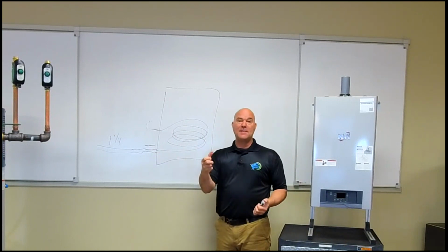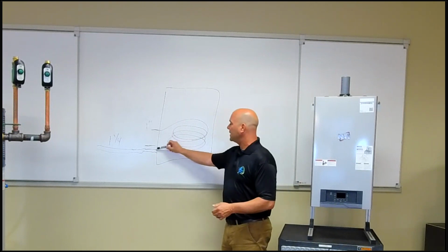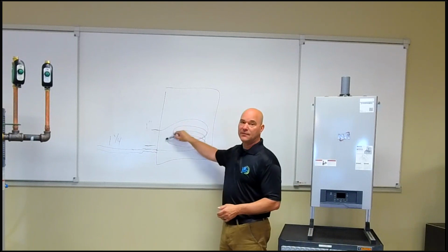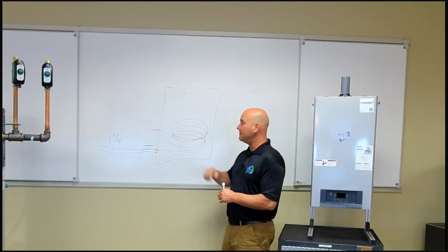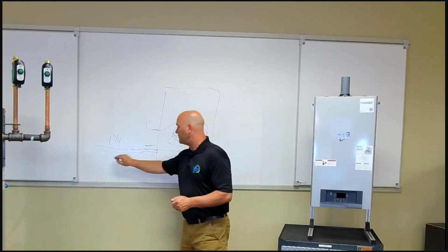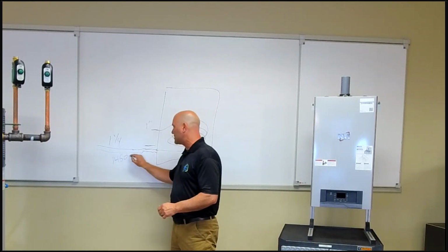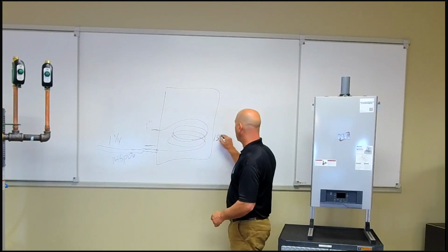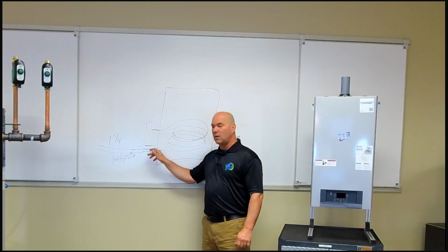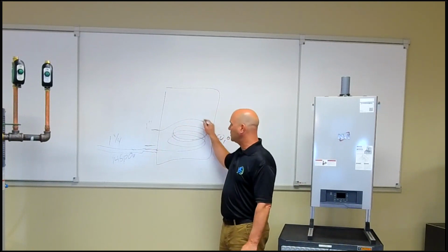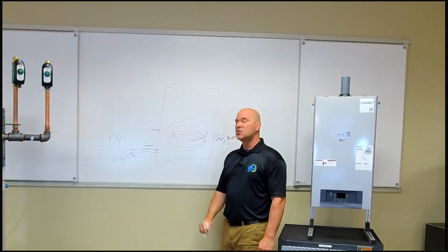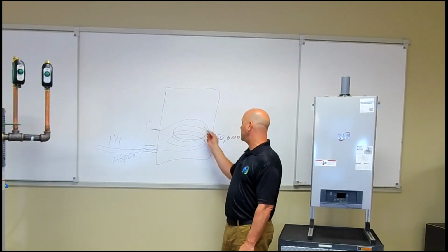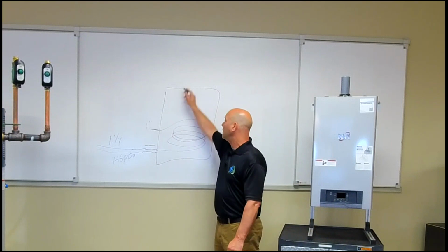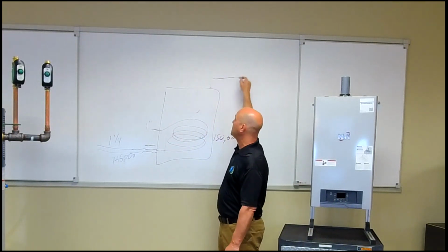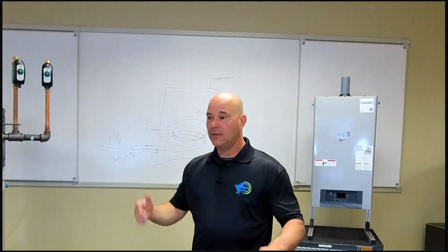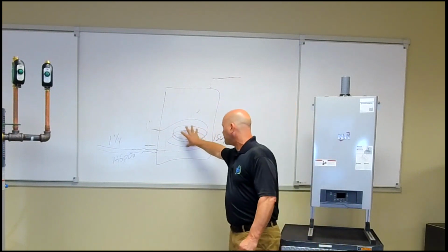So we're not making 90-degree bends inside of that tank. So what they've done is we're making circles in here. So we're not going to hear the velocity noises because we don't have that 90-degree bend, right? And in addition to that, let's call it 5 feet away, let's say we're getting 145,000 BTU over to it because we have the right size circulator. This coil can absorb 150,000 BTU. Well, it's only 1 inch pipe. So they add a couple of additional wraps in that coil so we have enough surface area to absorb the additional energy of the 150,000 BTU, and our cold water, whether it's coming in from the top, dropping down, running across the coil, heating up, and then being drawn out to the house, that's what's going on inside that indirect. So hopefully that makes some sense out of it for you, but the coils will be just a little larger.